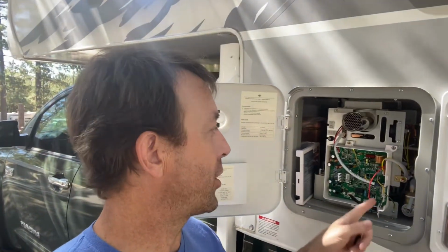So you'll want to check all those wires, because the second option, I misspoke earlier, is to come out and bypass that, to figure out whether the control panel or the ECO sensor is the problem. You're going to have to bypass the ECO sensor to make sure the connection wires are in good condition, but you should also check all your wires in here and fire it up again before you try to disconnect this or order a replacement, because that control panel is over $200.